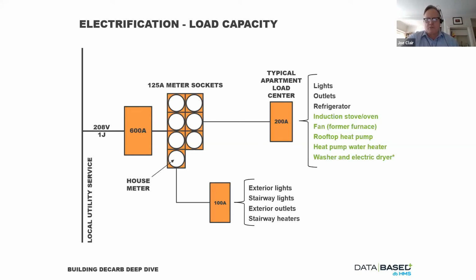That's the main electrical panel that all these different devices connect into. In most existing buildings, the stove has a minimal circuit plug into a standard outlet, so it has a very minimal draw. Your dryer also has a minimal draw for the rotating tumbler, but doesn't have everything needed for heat. When you add these things in, you go above what a typical load center can handle. So for a fully electrified residential unit, you'll need somewhere between a 150 and 200 amp load center, and in some existing scenarios that may be as small as 60 to 100 amps.